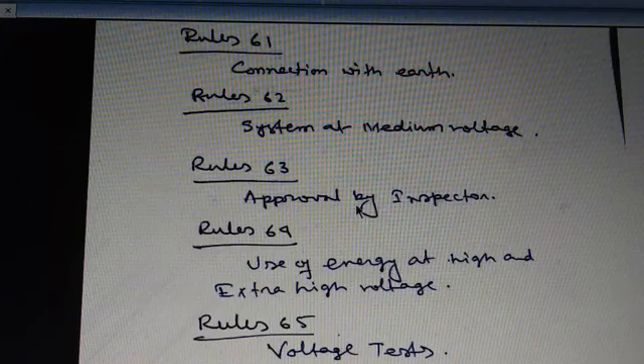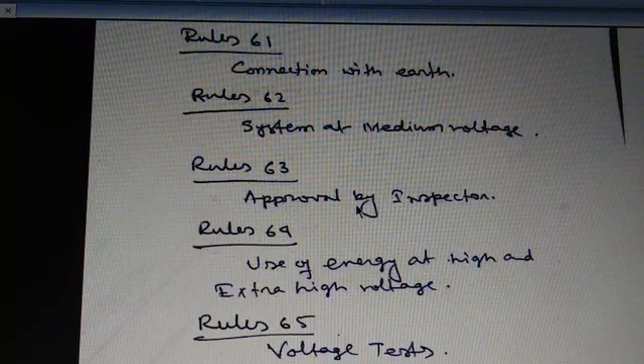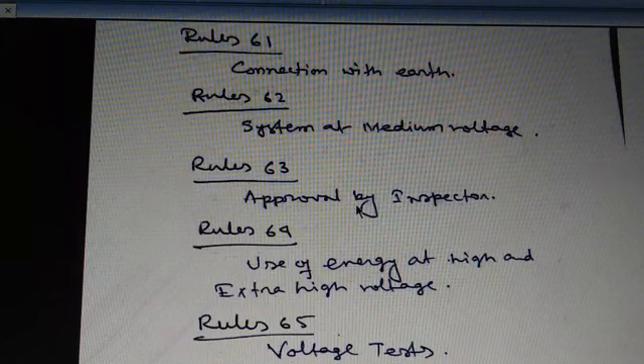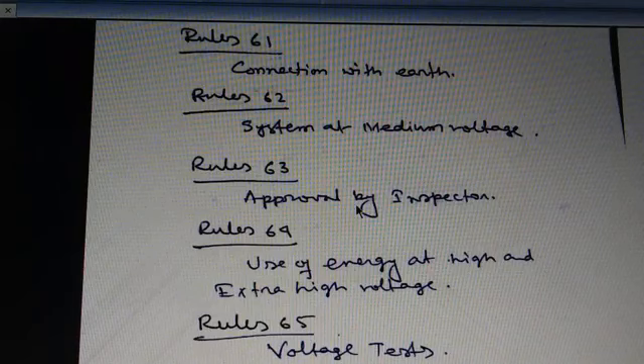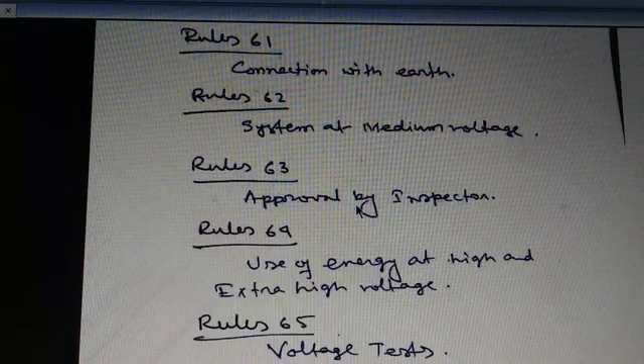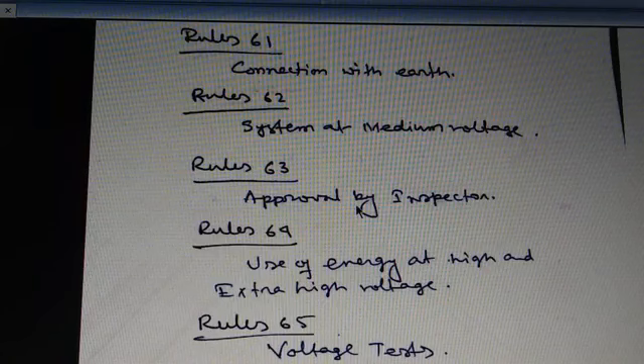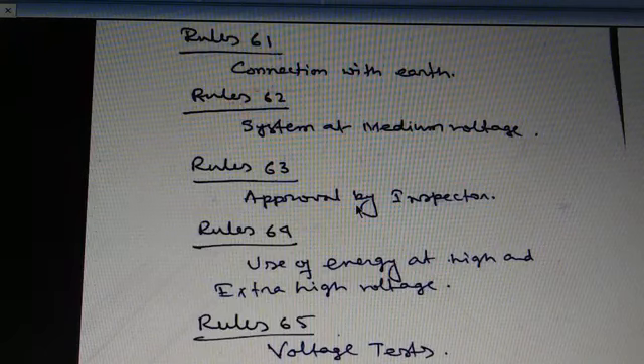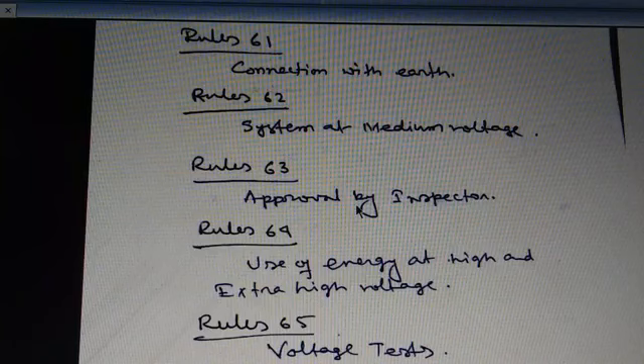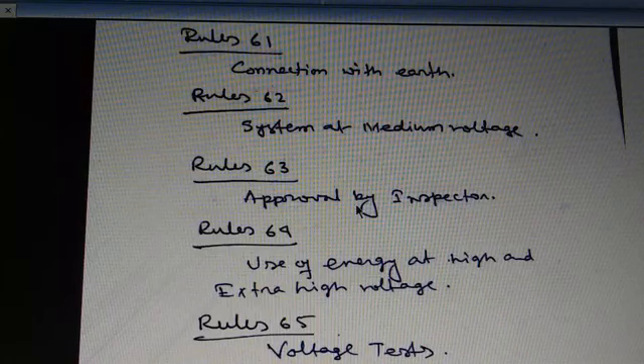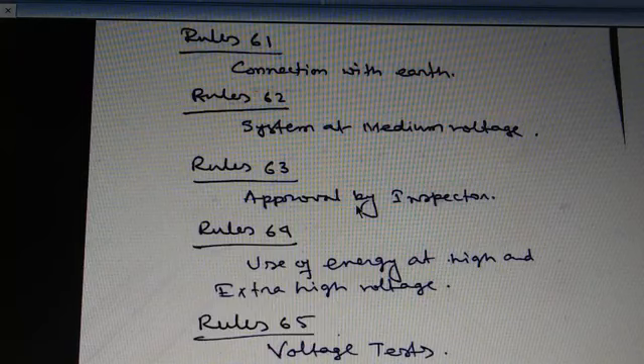The inspector shall not authorize a supplier to connect a supply of energy of high and extra high voltage unless all the conductors and apparatus intended for the use of high and extra high voltage and situated at the premises of the consumers are inaccessible except to the authorized person, and all operations connected with the said conductors and apparatus are carried out only by the authorized person. All the poles and types of substations are constructed and maintained in accordance with rule number 69.